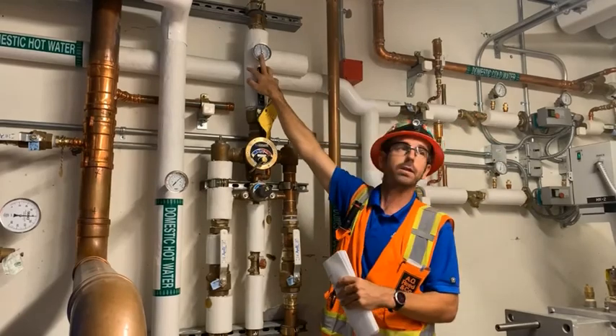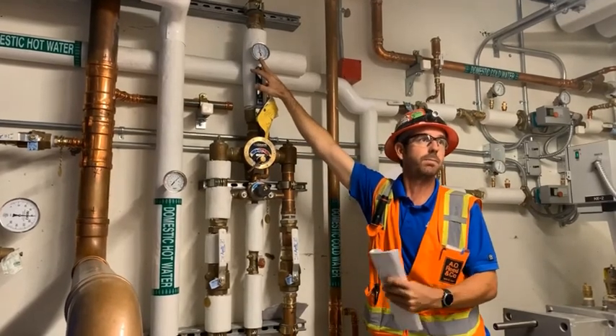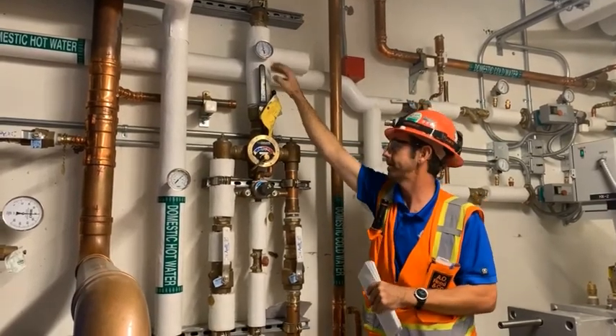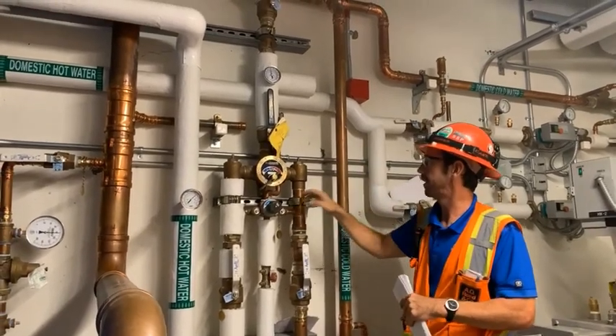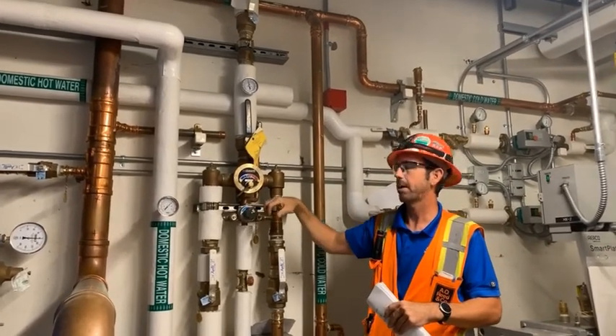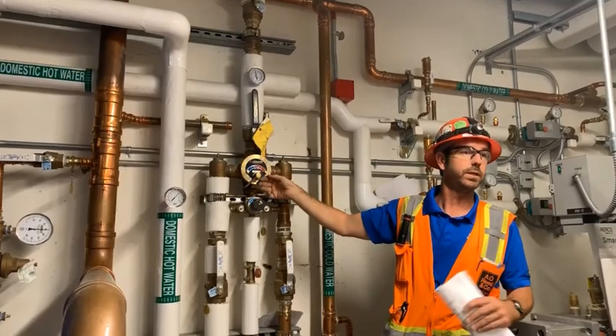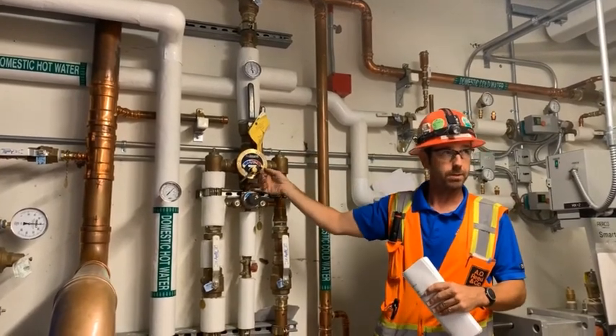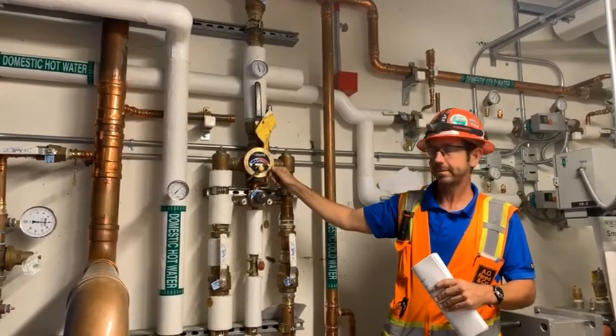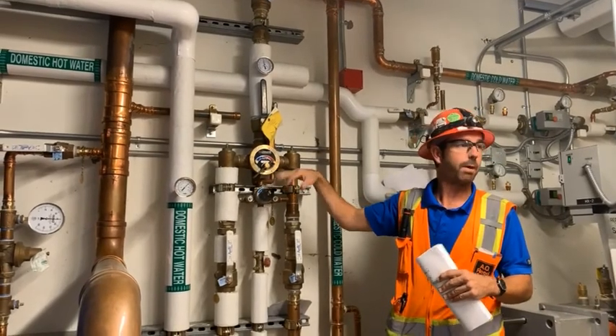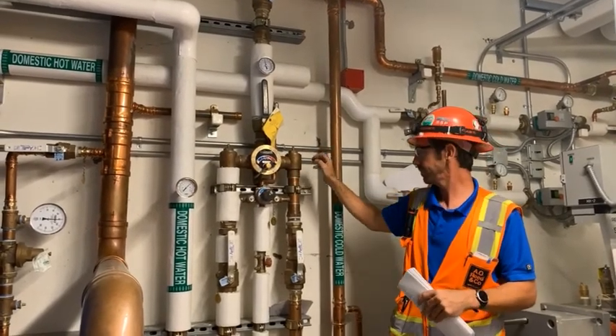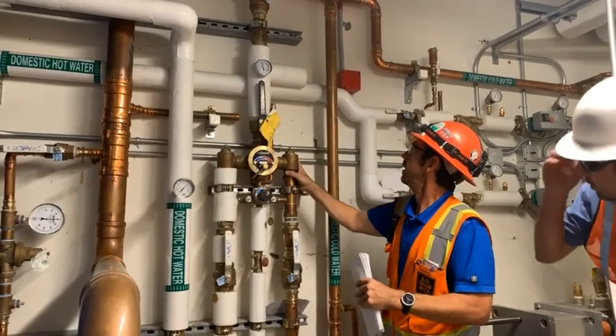We're using one outlet thermometer, okay? That way you know they're set the same. You're not reading 2 different outlet thermometers, okay? There is a set screw down here too, so don't come in here and just start cranking on that. If you do need to make an adjustment that you see this is drifting, you need to make sure you loosen that first, okay? But it is snug down so someone can't just accidentally bump that and change our settings, okay?